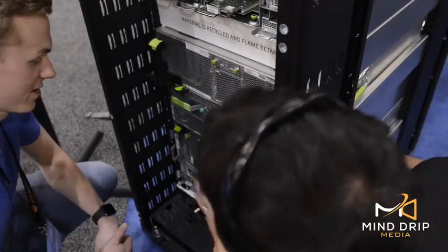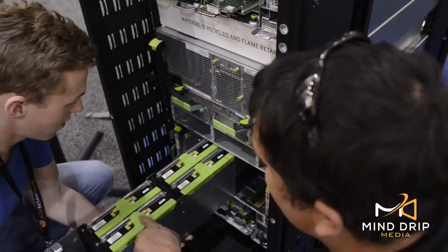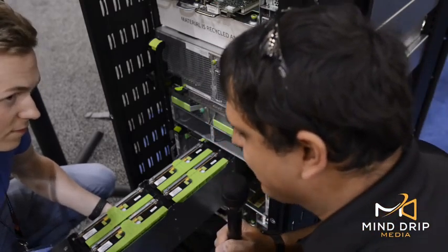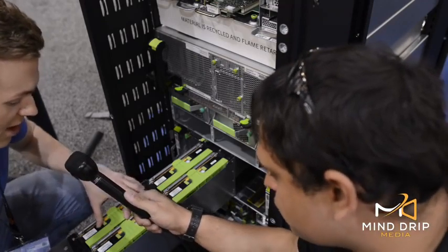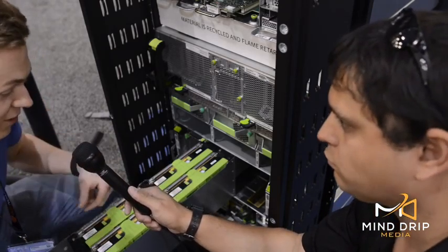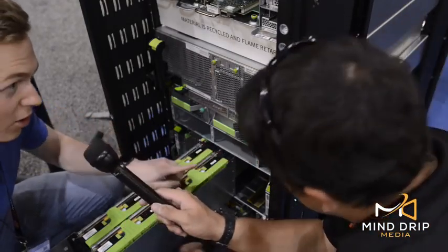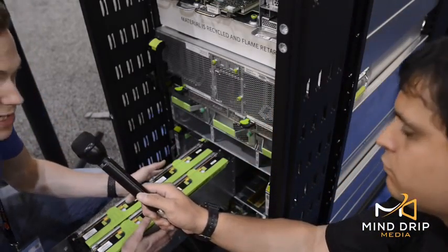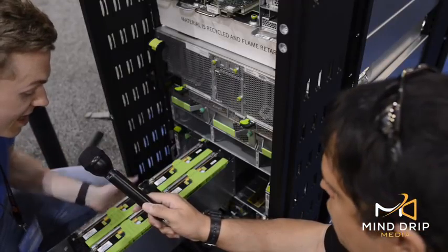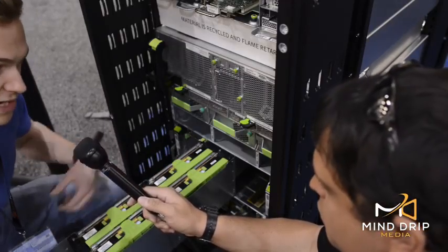There's an entire sled dedicated to those self-contained compute modules — it contains up to four compute modules. There's a backplane connecting all of them with a management controller and NIC, connecting all four computers to the network using centralized infrastructure. There's a power rail that runs all the way from the back to the front of the machine — all solid state, no extra cables. This provides power to the machines even when the unit is pulled all the way out of the rack, so you can pull an individual machine out and service it without taking the others offline or disconnecting them from the network.